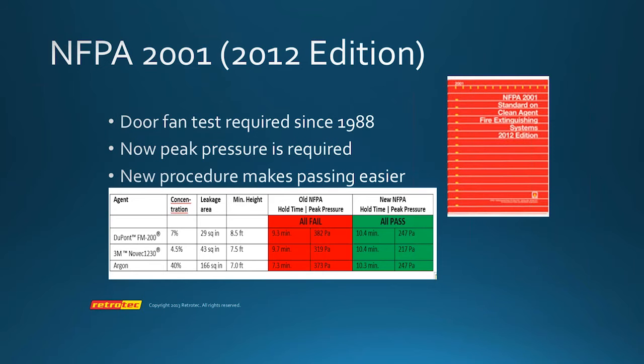There's some changes that I put through in the 2012 edition where we ran a different procedure. The reason why we changed the test procedure is so we could use the same test procedure to measure hold time, and that same procedure would also be used to measure the pressure venting. Since pressure venting occurs at usually over 100 pascals, the leakage of enclosures at higher pressures are often quite different than they are at lower pressures. So it actually helped in both regards.